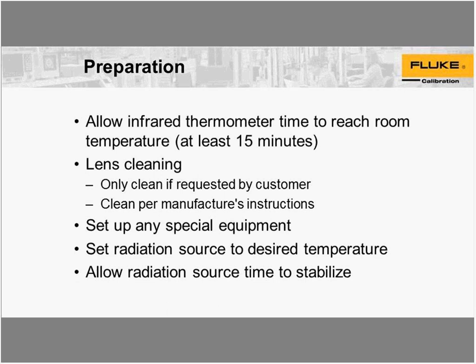The second thing is lens cleaning. I don't recommend that any of you try lens cleaning on an instrument — this can be very risky for your laboratory and may put you in some liability. That said, if you need to clean the lens, only clean it if it's requested by the customer or if the customer knows about it. When you do clean the lens, clean it per the manufacturer's instructions. These instruments are optical instruments — just like if you don't clean glasses properly you can damage them. If you don't clean the lens properly, you can damage the optics and the instrument won't measure as well. After that, consider setting up any special equipment such as a dry air purge, an aperture, etc. Set your radiation source to the desired temperature and allow it time to stabilize.